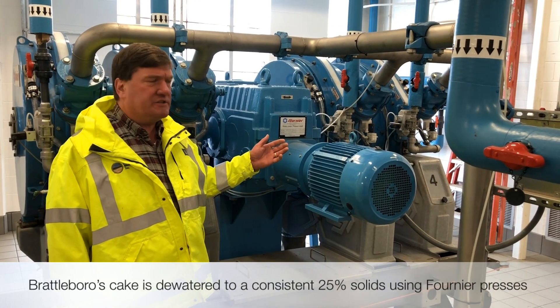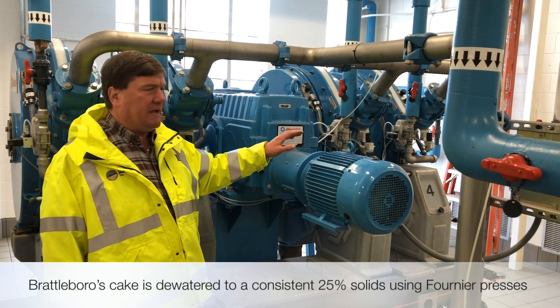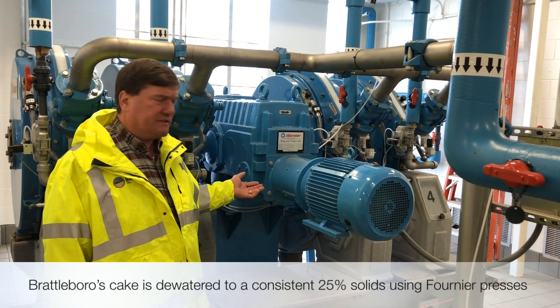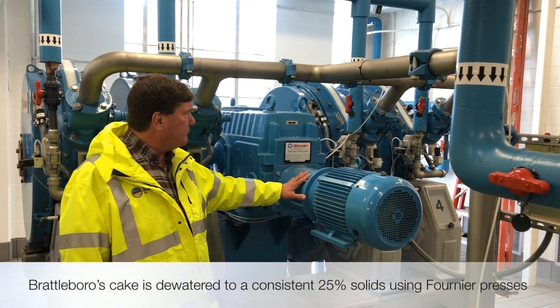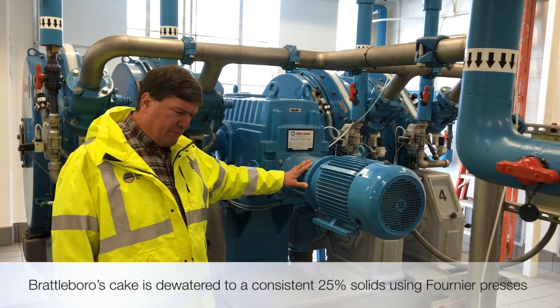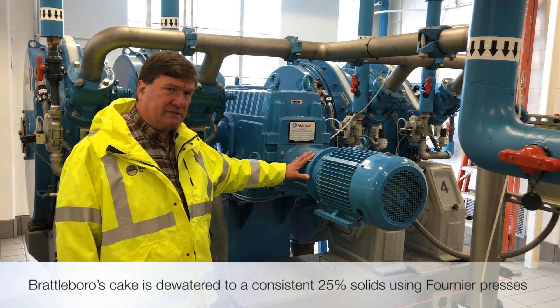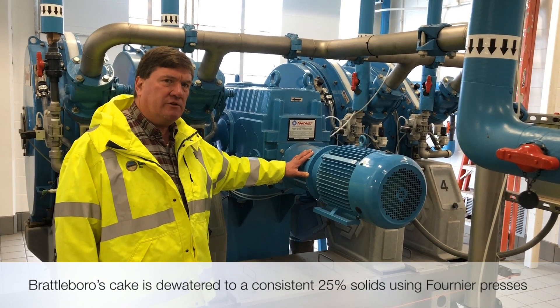After the sludge comes off process, it gets sent to the anaerobic digesters. The wet solids are dewatered using Fournier rotary presses. These Fourniers were installed approximately eight years ago and put out a consistent 25% cake. The thing to note is that when you're interested in drying the sludge, the more you can dry it mechanically — with a press — the less energy it will take to dry and the more product you can move through your unit.